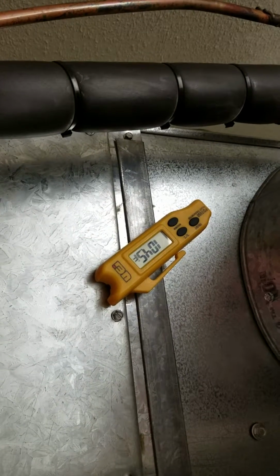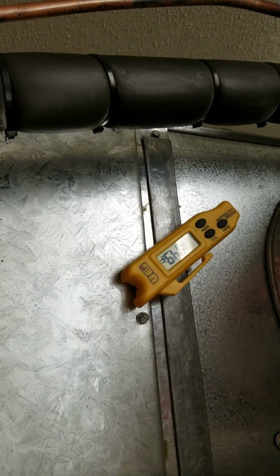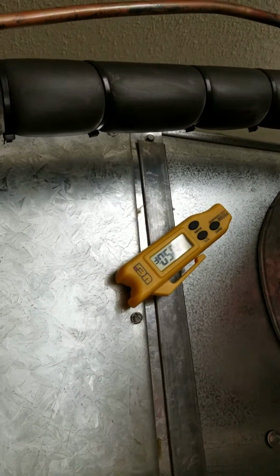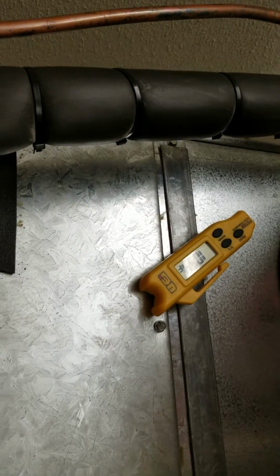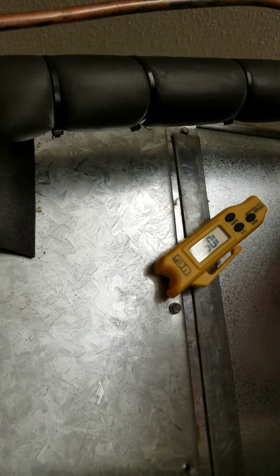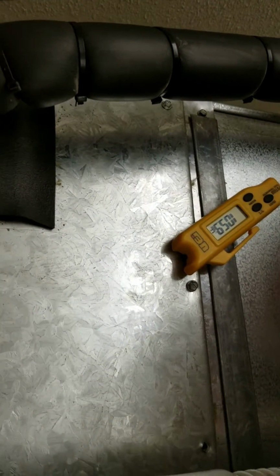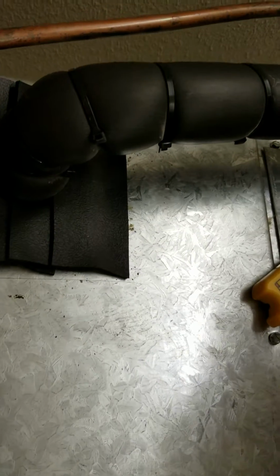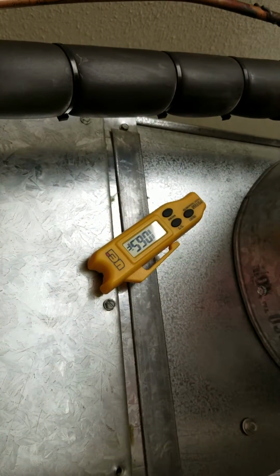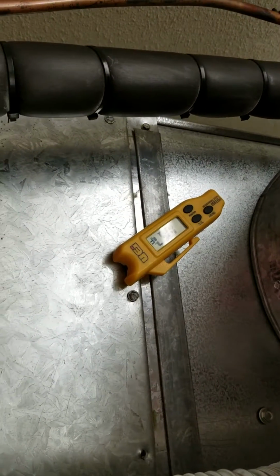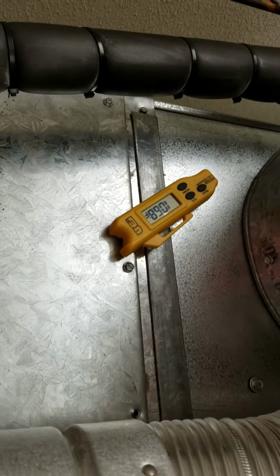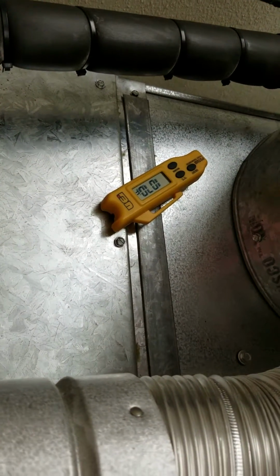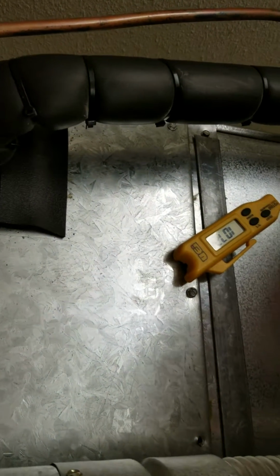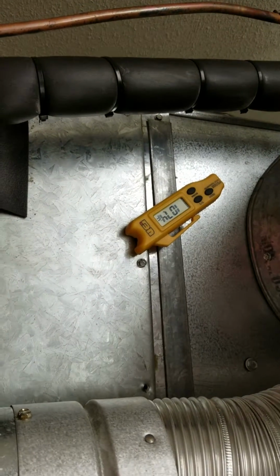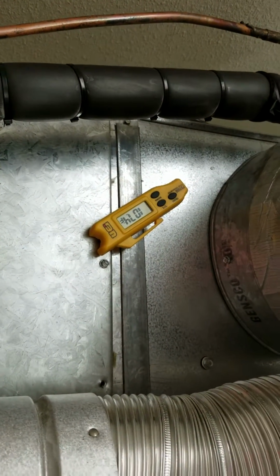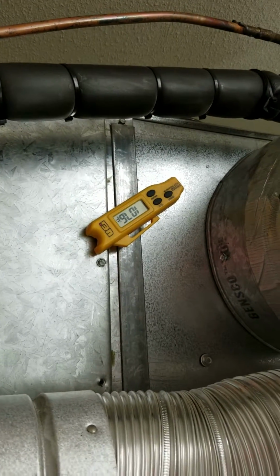If we find that it climbs way above our expected temperature split, we start looking for things like a blower turning backwards, a plugged evaporator coil, or again, where we look down here, insulation falling off and blocking the ductwork, because these require airflow in order to work. And we are at 107 and still going up a little bit. This one should go up to about 112, which is going to put us right in the middle of our range at about 40 degree temperature rise.